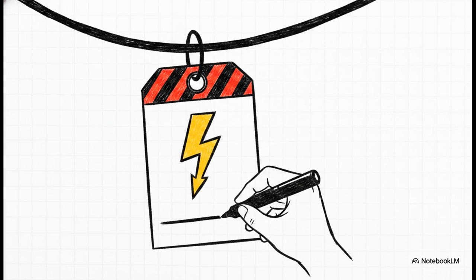Right alongside that lock goes a danger tag. These are literal lifesavers. They've got to be red and black on a white background, dated and signed by the worker. Crucially, they need to list specific hazards. If you're working on a modern site, writing something like multiple points of supply on that tag warns everyone else that flipping a switch could reconnect an alternate supply and endanger your life.